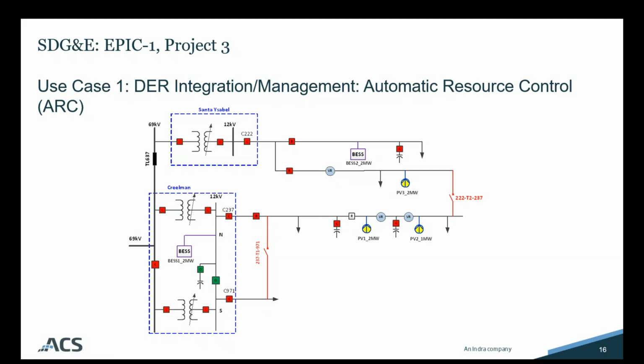So the first application that they wanted to utilize automatic resource control was doing a volt-var optimization, or VVO scheme. Now, VVO has been around the industry for quite some time, and it's been utilized to reduce system losses and make the feeder more efficient. However, another reason for coordinating all these devices is to allow for a more optimal operation system, not only to reduce losses, but also flatten the voltage profile.